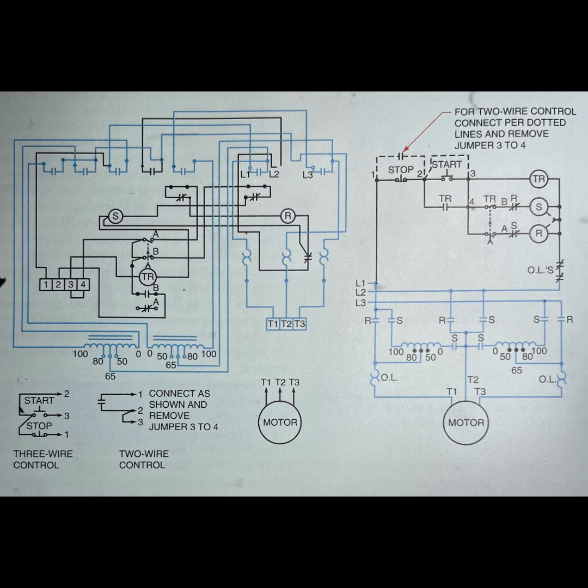After a preset time period, the normally closed TR contacts open and the normally open TR contacts close. When coil S is de-energized, normally closed interlock S closes and energizes the running starter. The contact switching arrangement for a typical power circuit can be seen in the next image.